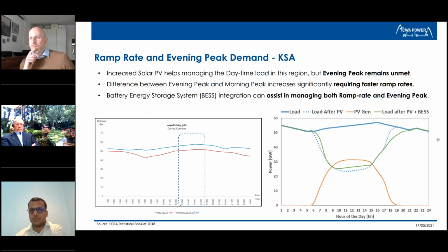The substations, the transmission lines, all of those can be commonized, and hence the effective cost of energy storage can be reduced by coupling at the DC level or at a medium voltage level between PV and BESS. Looking at a futuristic scenario, it might be prudent for regulators or utilities to start introducing such flexibilities, considering the targets being set by various countries in the region.